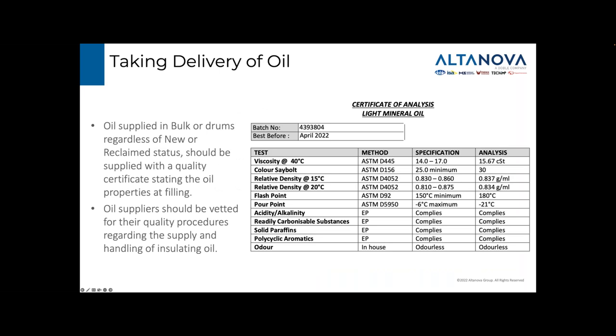Having selected and ordered your oil, it should come with some documentation detailing the type of oil, the filling dates, batch numbers, and the standard to which it adheres, e.g. IEC 60296 for unused mineral oil, and the specification of the supplied product. Be wary of wording on these forms, "will meet" or "will meet specification", when not supplied with actual test values, as you can see on the right of this table under analysis.